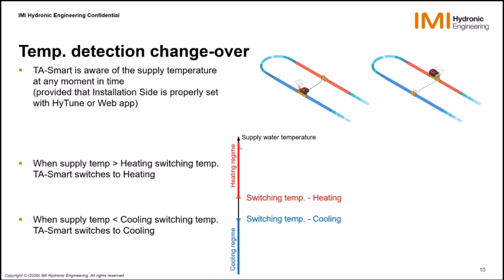and continue its control according to the correct maximum value. So there is only a little transition in time where we might be in a situation of, when the valve is closed and the switching has been made, we have changed the way we warm up or cool down the water. It's only in these few moments that we are going to be in a situation of not being exactly as the system is set up at the defined moment.